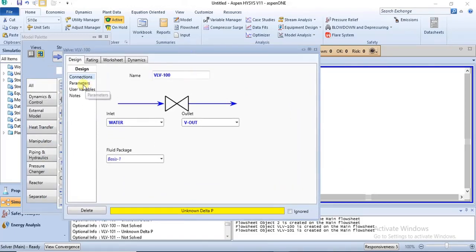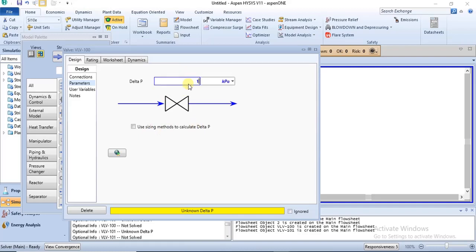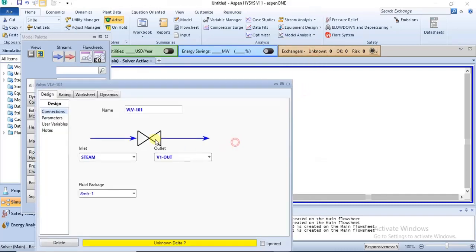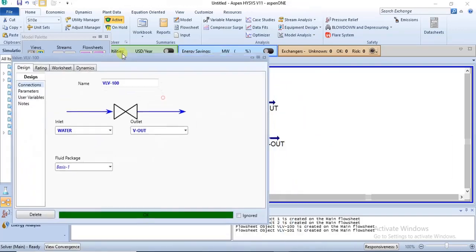Once you specify the pressure drop, the valve should solve. For the pressure drop specification, you can either enter it manually or use sizing methods to calculate it. However, to use the sizing methods, you must enter a manual value first, size the valve, and then switch to that option. I'm using a pressure drop of 10 kPa for both valves, and both have now solved.